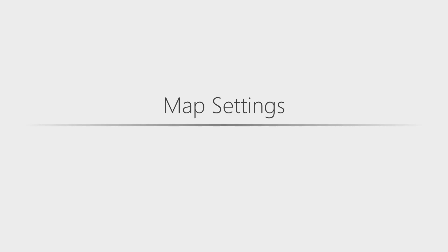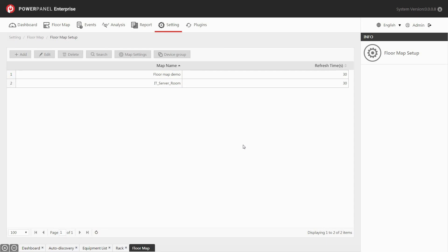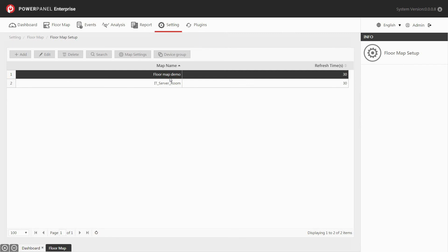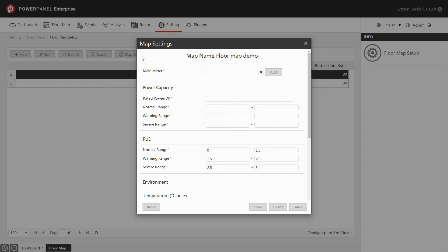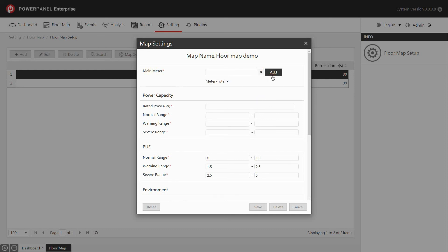The map settings allows you to manage the power capacity, PUE, environmental data, and facility utilization of the data center. In the floor map page, select the map that you would like to set up, then click map settings. Select and assign the main meter from the drop-down list to calculate the total energy consumption of the floor map. Then click add. Set the maximum power rating of the floor map, and then set the range of the output power values for normal, warning, and severe status.